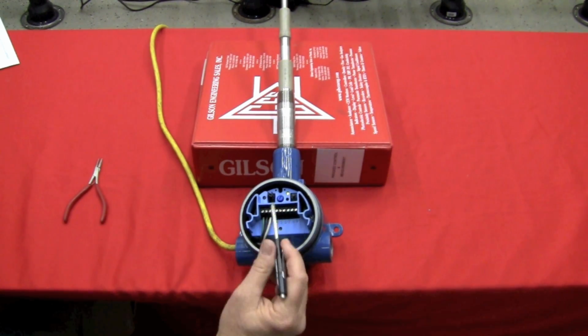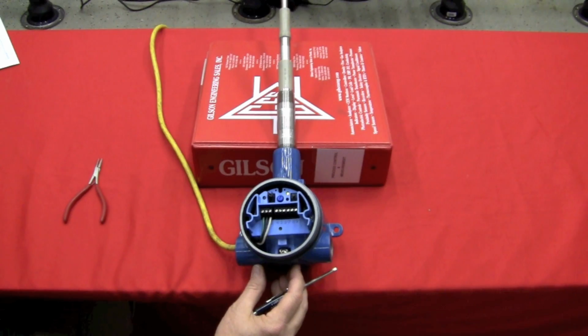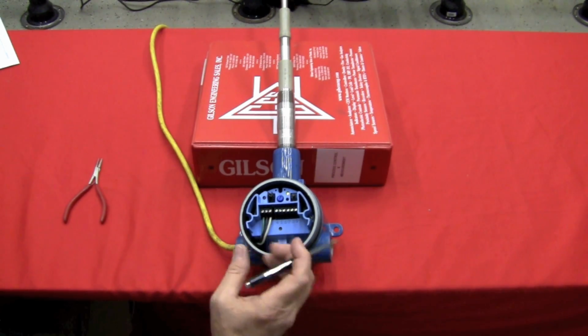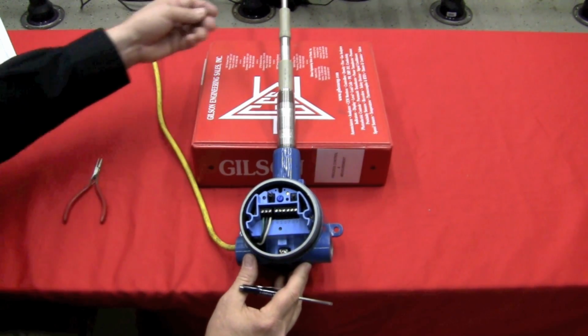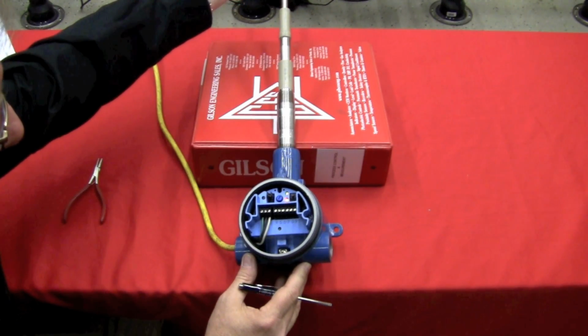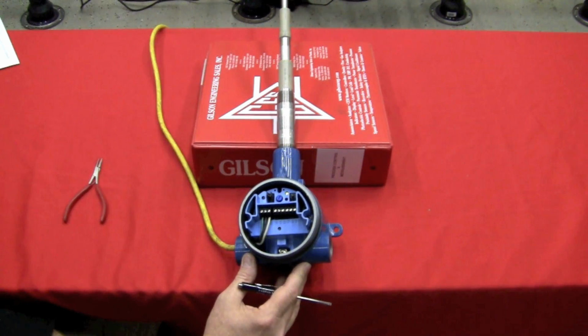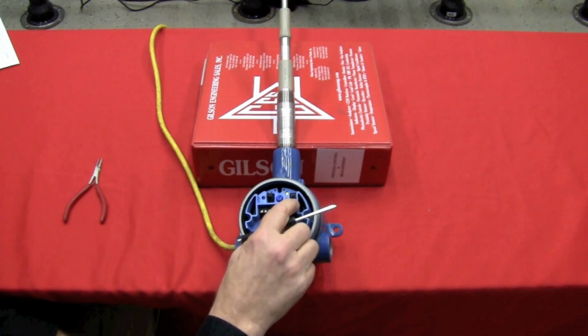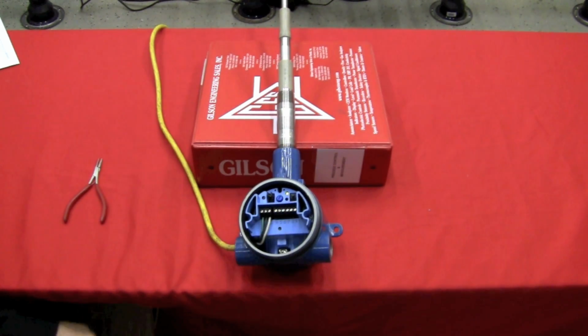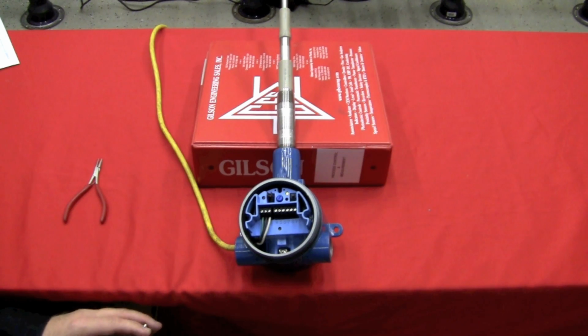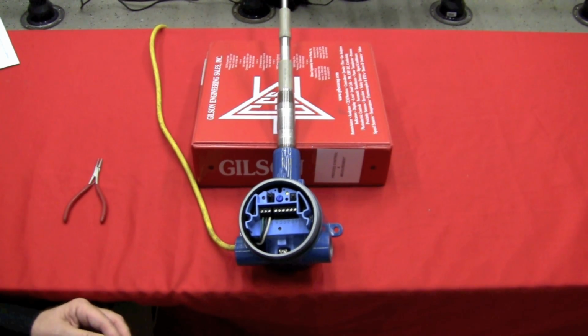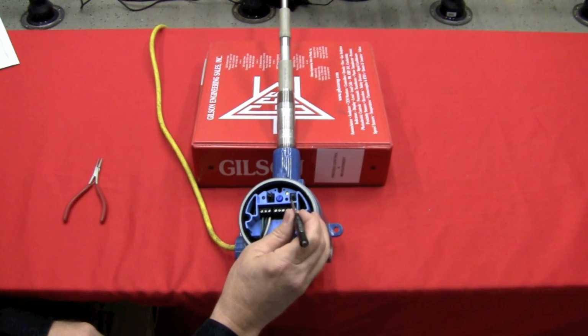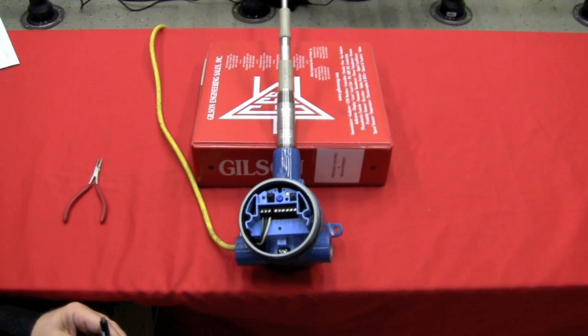You'll see two LEDs. The top LED is green, which indicates power. The LED below it is red, and I'm going to reach and grab the probe and put it in alarm, and you'll see that the alarm light comes on. When I release my hand from the probe, the alarm goes out. And then finally, we have a button on the far right, which is our recal button, and we'll use that during the calibration, and I'll explain that in a bit. And finally, we have a 3-pin jumper below the cal button, and that's also used to set the calibration mode, and I'll explain that in a second as well.